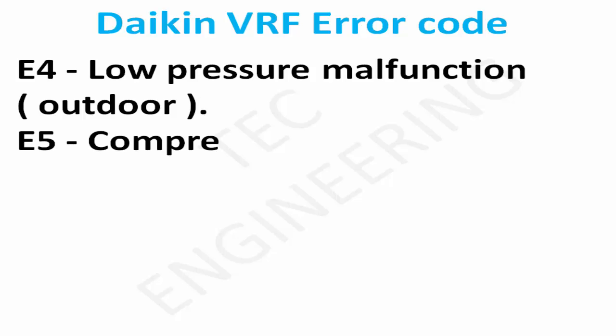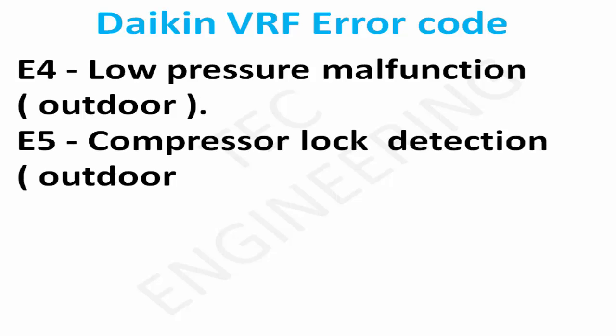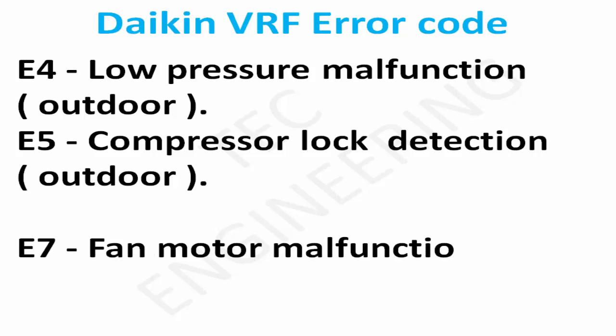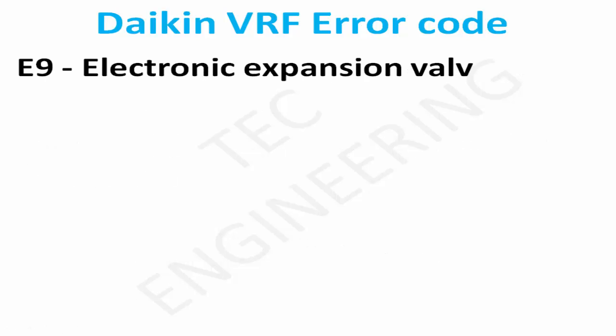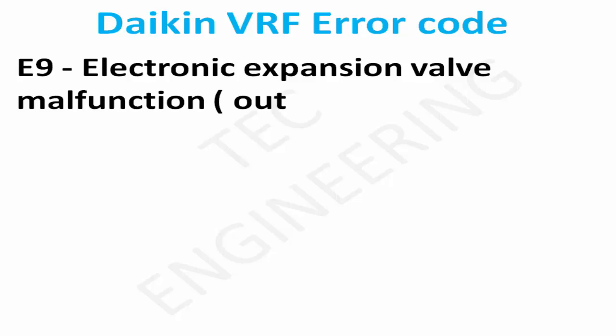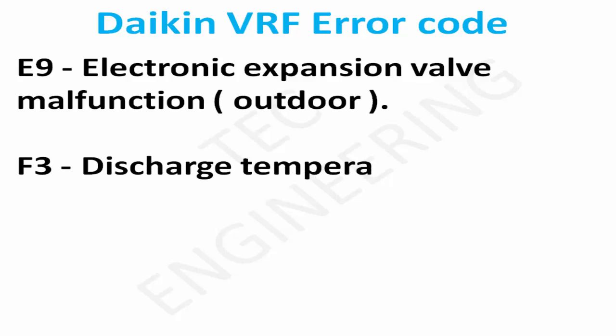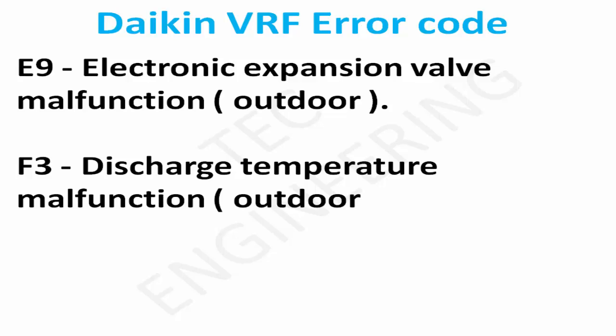E5: Compressor lock detection, outdoor. E7: Fan motor malfunction, outdoor. E9: Electronic expansion valve malfunction, outdoor. F3: Discharge temperature malfunction, outdoor.